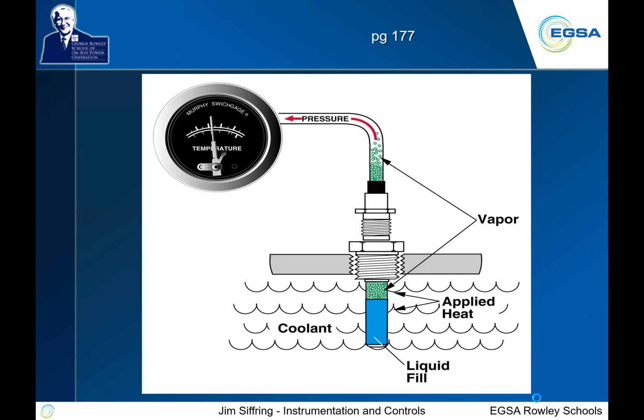This graphic I always find important because what you're looking at is this. So what we're looking at is temperature. You'll notice the Murphy Swichgage there says temperature on it. But then you look back at the graphic and it says, well, we're applying pressure to that temperature gauge. That doesn't seem to line up.